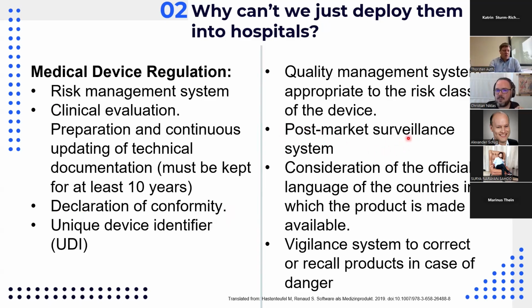You do need to do post-market surveillance, so you have to be careful what happens after you put your product to the market. You have to provide the documentation in languages of all countries that your product is used in. So in the EU, that's quite a lot of languages, especially if you want to provide it for the whole EU. And obviously, you have to be able to recall products that are harmful to patients. So this is only the MDR.